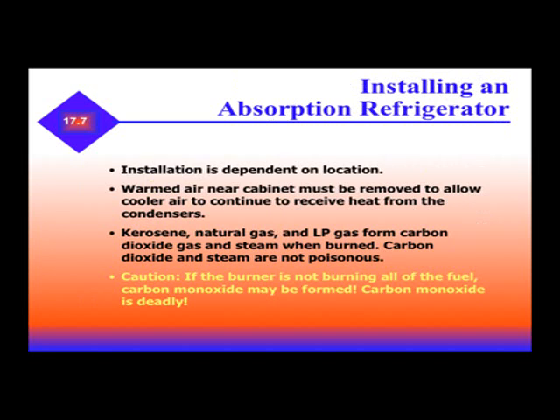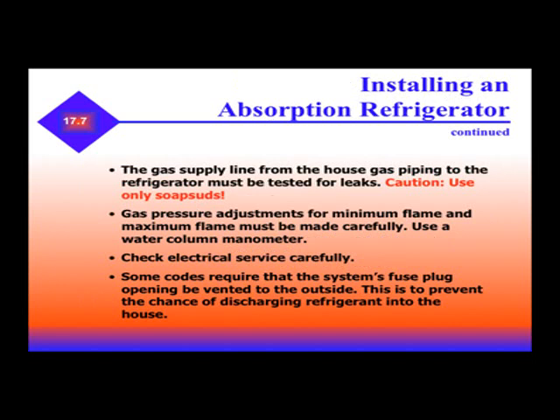When installing an absorption refrigerator, installation is dependent on location. Warm air near the cabinet must be removed to allow cooler air to continue to receive heat from the condensers. Kerosene, natural gas, and LP form carbon dioxide and steam when burned — these are not poisonous. However, if the burner is not burning all the fuel, carbon monoxide may be formed, and carbon monoxide is deadly. The gas supply line must be tested for leaks using only soap suds. Gas pressure adjustments for minimum and maximum flame must be made carefully using a water column manometer. Check the electrical service carefully. Some codes require that the system's fuse plug opening be vented to the outside to prevent discharging refrigerant into the house.